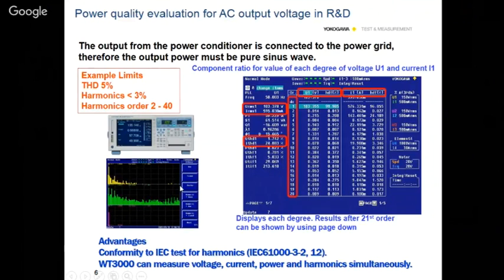But actually, if you do the detailed analysis, I don't think any of the parameters is meeting it. THD is going up to 28% in places, and harmonics should be less than 3%. In some it is going up to 24%, and the harmonic order should be less than 40, but it is more, even up to the 100th or 120th order it is present.